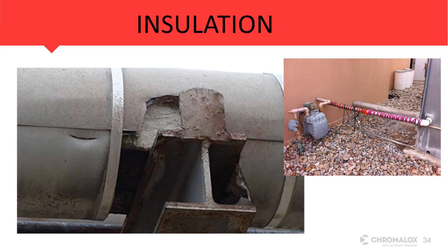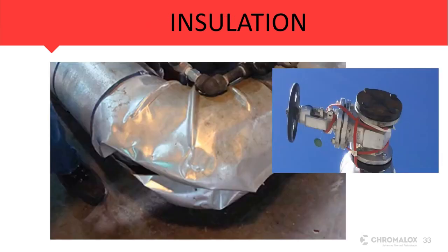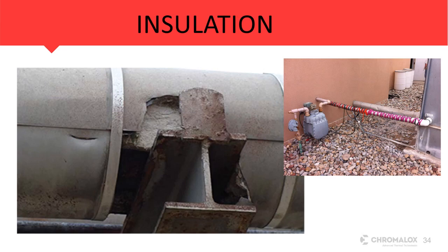And of course, heat tracing does require insulation. You typically are not going to be able to get to your set point unless you insulate a line. Someone asked me before, well, can't I just put the heat tracing on? I don't need insulation. I liken that to telling them, if it's 32 degrees outside and you turn the heater on in your house and take the roof off of your house, you're not going to be able to maintain a comfortable temperature. Same thing applies for heat tracing. It has to be insulated. There's no getting around that.